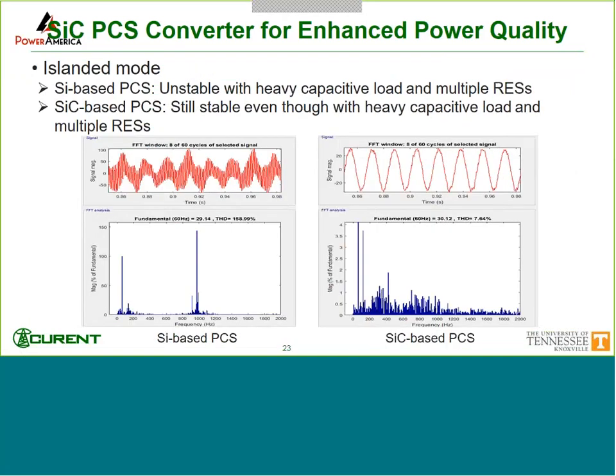For islanded mode and the microgrid, the PCS will not provide power, so it's just sitting there not doing anything. So you could use it as a stability enhancer. So in this case, again, if we have some unfavorable load condition that does not match well with battery or other energy sources or PV energy sources, and assuming those sources do not have the bandwidth to deal with it, in this case, our PCS converter would be able to help with the stability as it's shown here, right? This is silicon-based versus silicon carbide-based case.